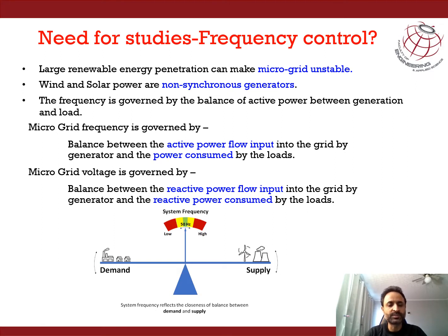to control the frequency. Frequency in a microgrid or in any grid is actually given by the balance between the active power generation by the generators and the active power consumed by the load. Whenever there is an exact balance between the active power generation by the various generators and the active power consumed by the loads, the frequency will be constant. Whenever there is an increase in demand in the load and the generation of active power is less, then the frequency will drop. Similarly, the frequency will increase when the load is reduced.